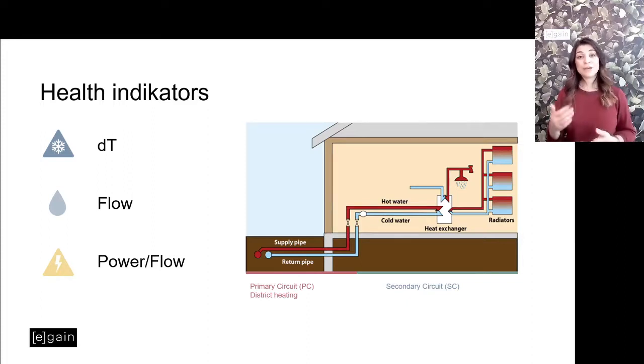A measured high flow can indicate leakage in the primary or secondary circuit, but it could also tell us that we have a badly adjusted system between the primary and the secondary system.